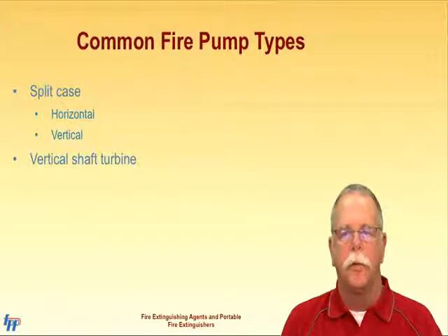Split case pumps are pumps whose housing comes apart in the middle for repair. The pump in a fire engine is considered a split case pump. Horizontal or vertical refers to the orientation of the impeller shaft. Therefore, the pump in your engine is a horizontal split case pump.